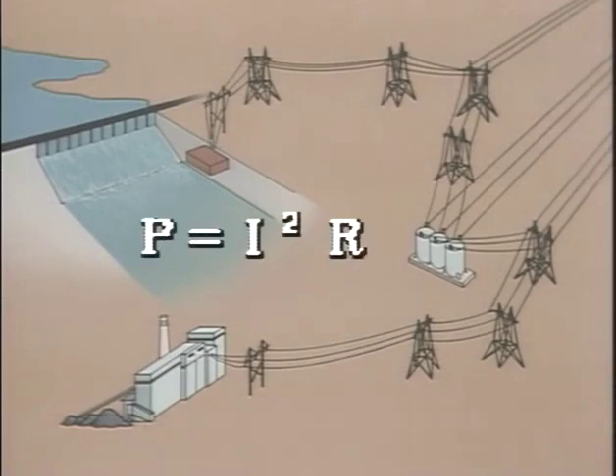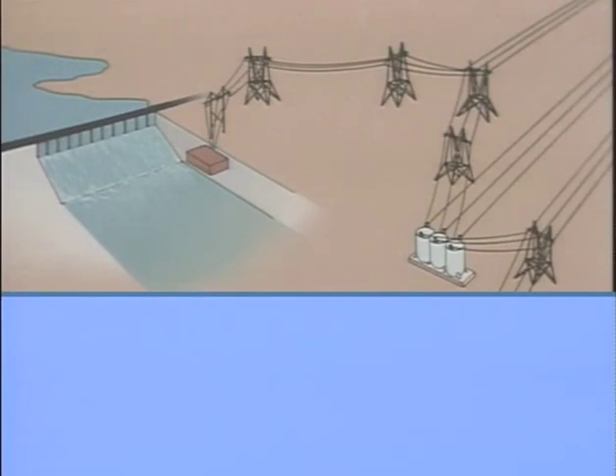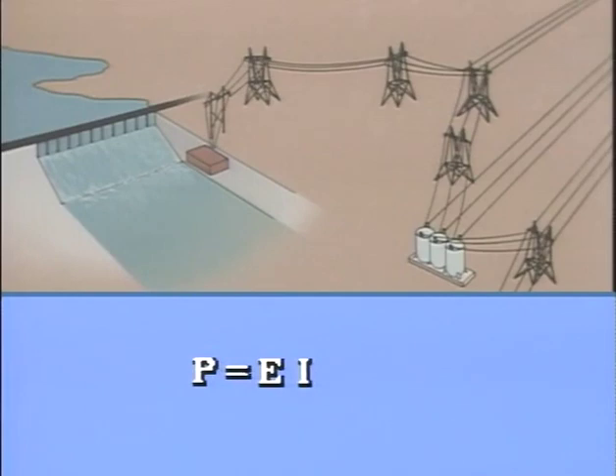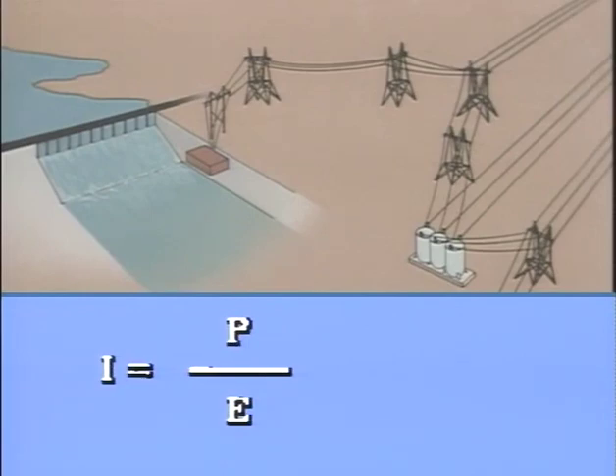By using the equation P equals I squared R, we can determine the power loss for each system. For each system, we already know the voltage — 250 kilovolts and 500 kilovolts — the power, 50 megawatts, and the resistance, 5 ohms. In order to determine the power loss for either system, we first need to find the current. Let's find the current for the 250 kilovolt system first. We'll use the power equation P equals E times I and rearrange it to solve for current: I equals P divided by E. Substituting the known values, the equation reads I equals 50 megawatts divided by 250 kilovolts.